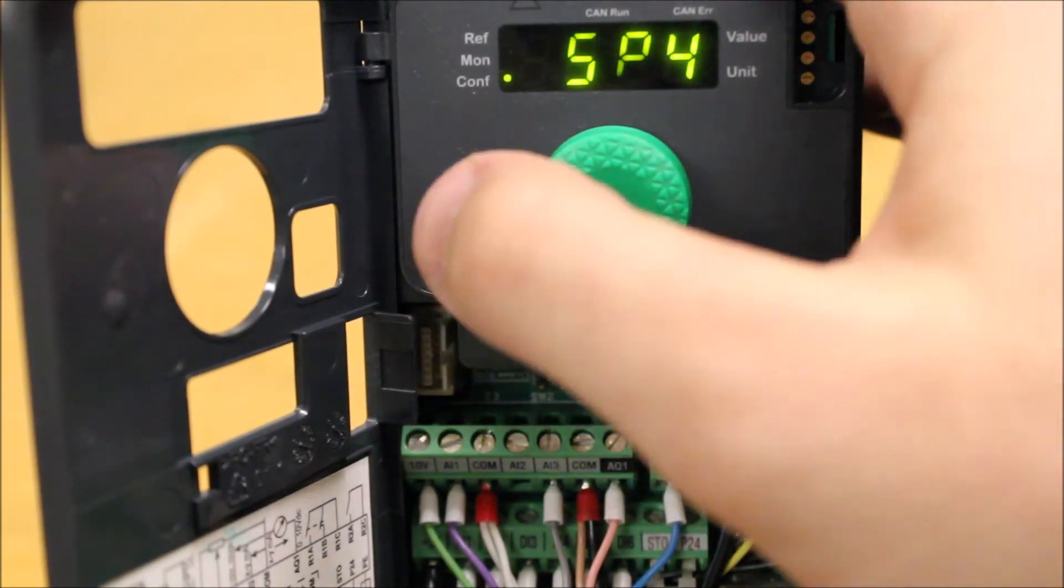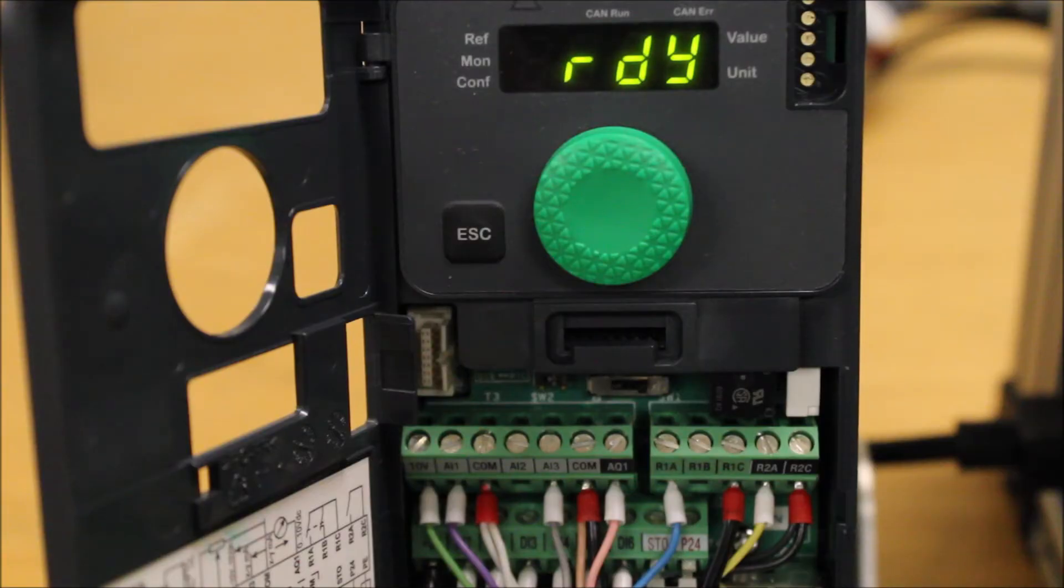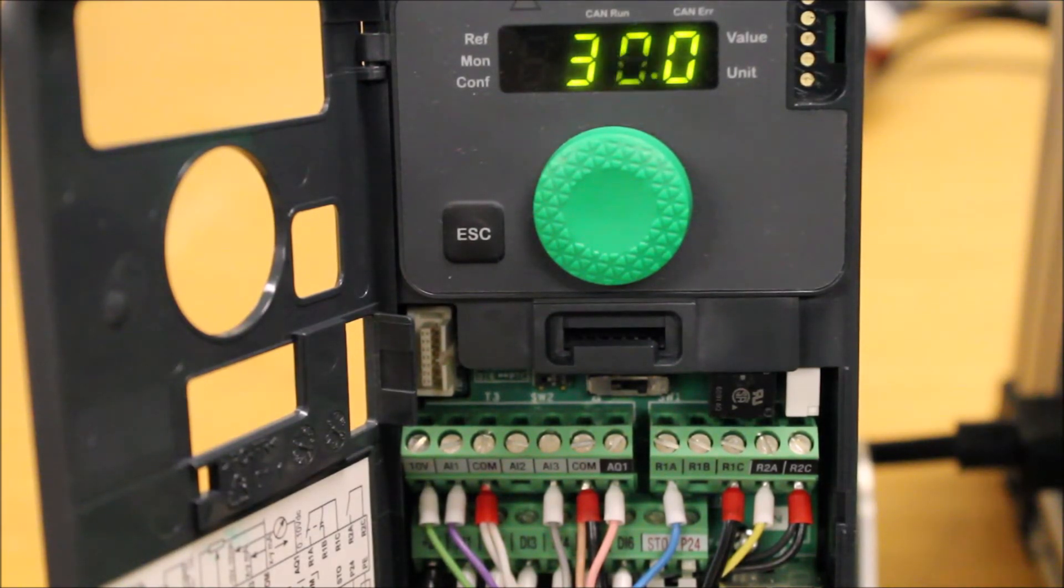Once it's all programmed, you can escape back out to your main screen, give it a run command from DI1. And with the first preset, which is DI3, it'll go to 30. With the second preset, it'll go to 60. And with DI3 and DI4 turned on, it'll go to 45.